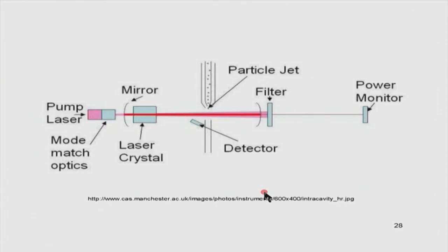How you keep them far apart is that even if you take, for example, smoke, which has a very high concentration of particles, you have to dilute the smoke sample with clean filtered air so that the particles are separated far enough that they pass through the laser beam one at a time. Okay? This is typically the cross section.